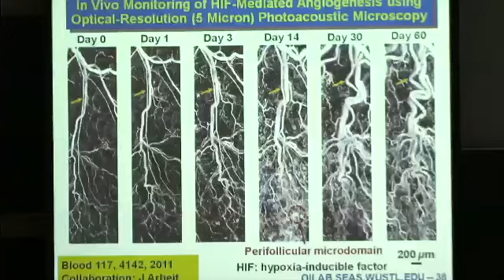That first device was a 5-micron resolution version. We improved the resolution to 2.6 microns. You can image the entire ear of a small animal using intrinsic contrast only. Right. This image is so dense, you have to zoom into a small area that allows you to see capillary beds, single capillaries. All these single dots are single red blood cells. So we have single cell resolution, single cell sensitivity, using intrinsic contrast only. If you were to use micro X-ray CT, you have to inject contrast agents. Even with exogenous contrast agents, you still miss capillaries because there's not enough contrast for you to image with. This is a 3D rendering.